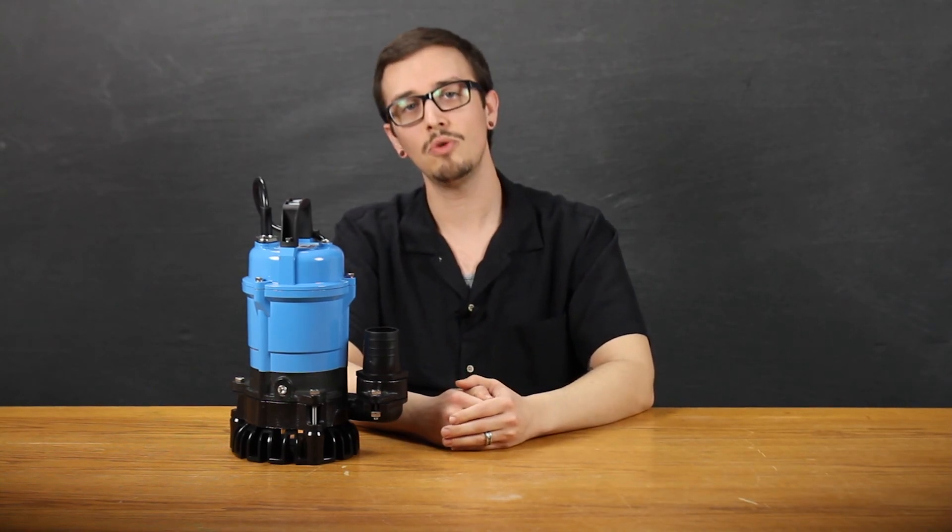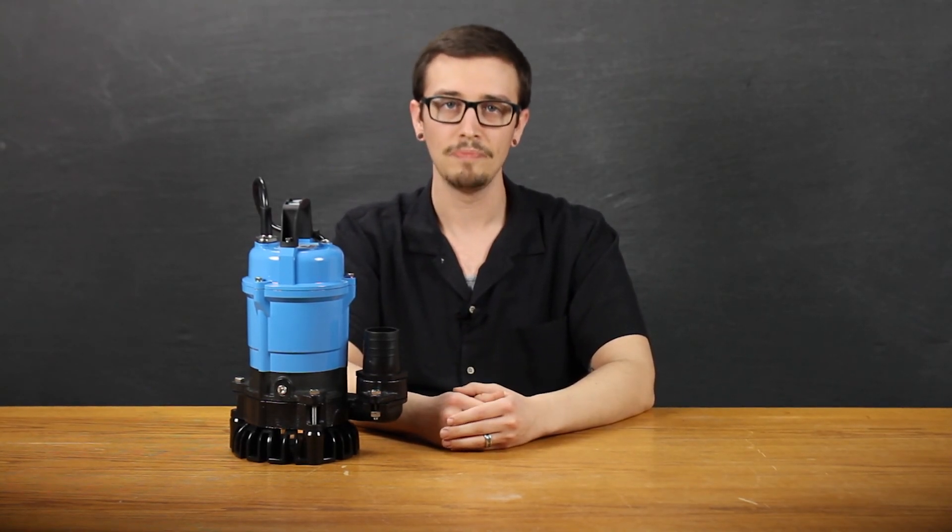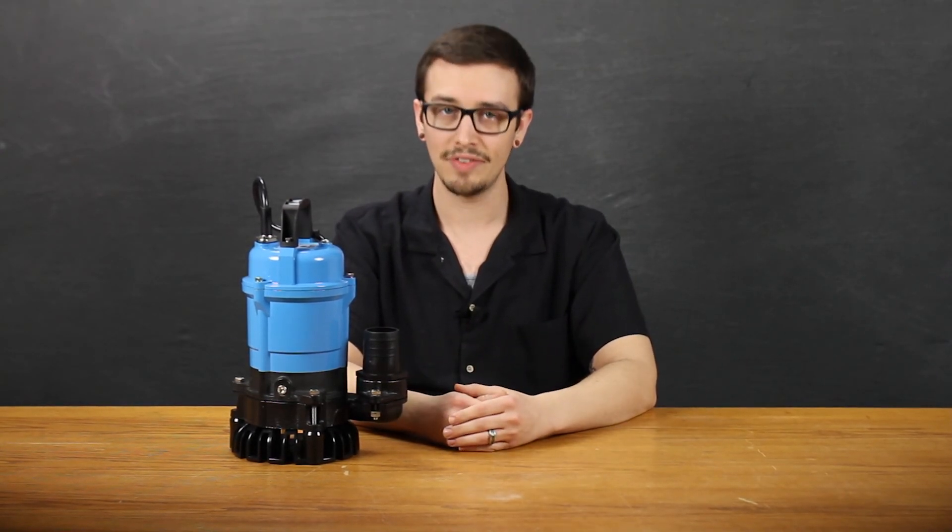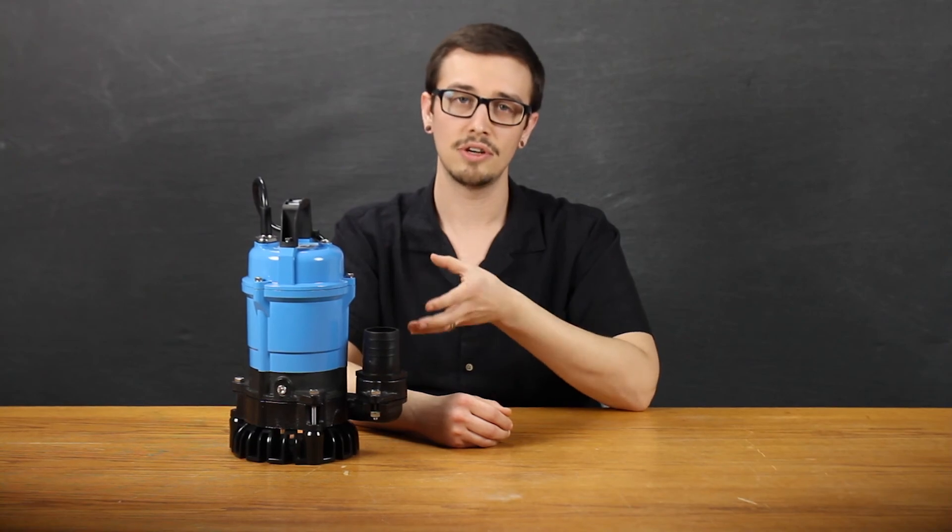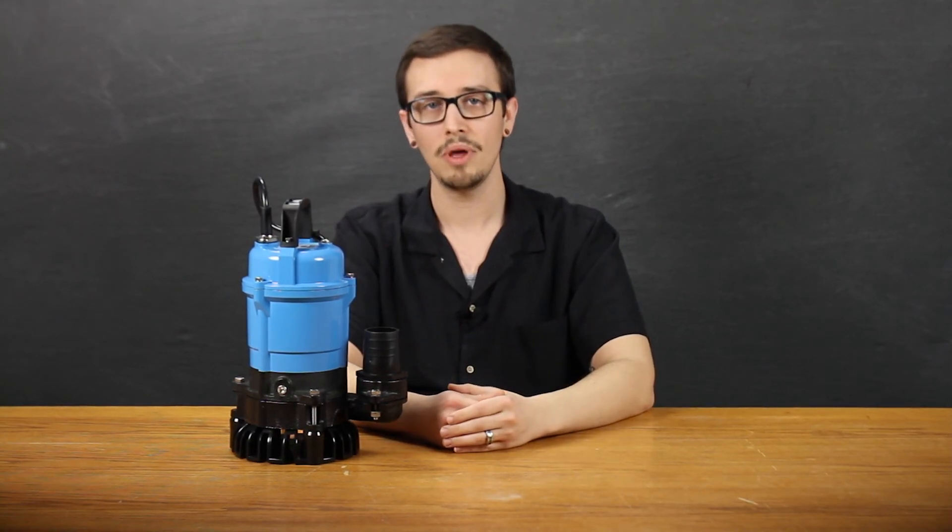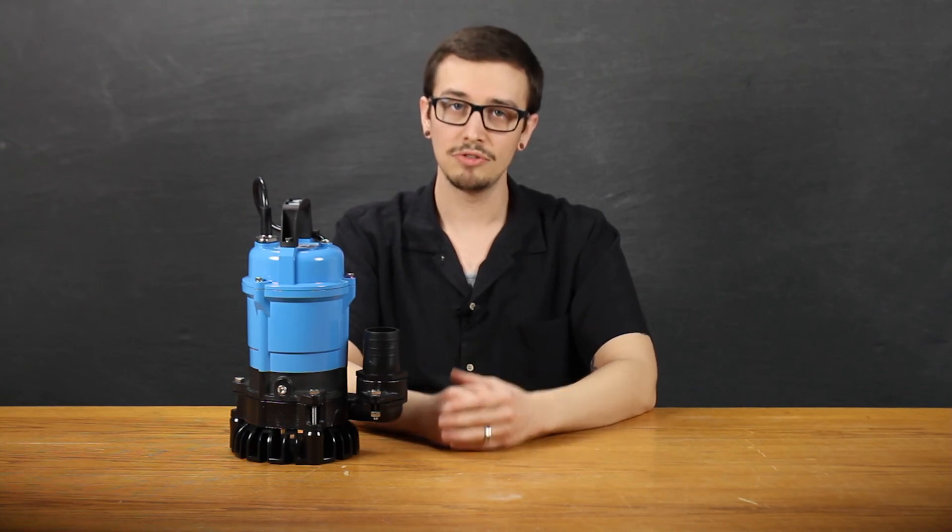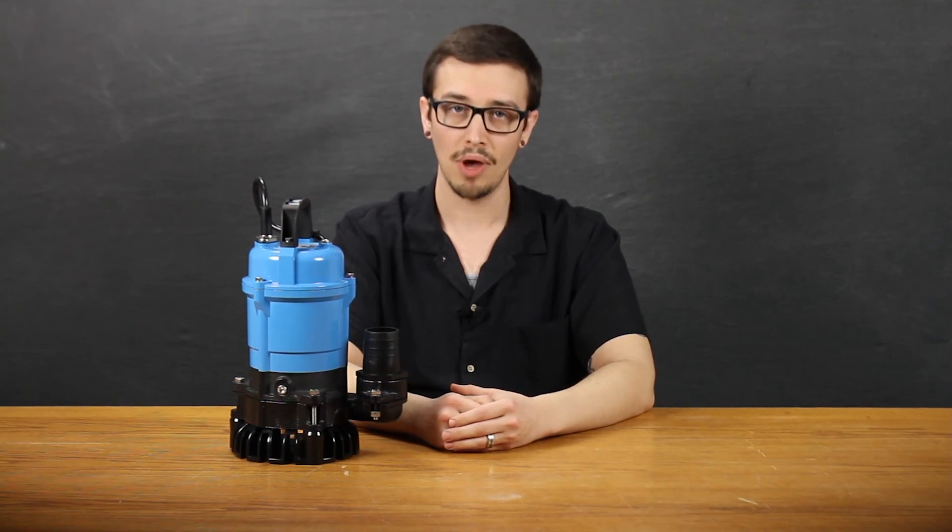The pump comes standard with a 2-inch NPT discharge, and it is rated to handle solids up to a half of an inch. Though solids are not necessarily the intention with this pump, it is well-equipped to handle those occasional solids and features a semi-open 8-vane vortex recessed thermoplastic impeller.